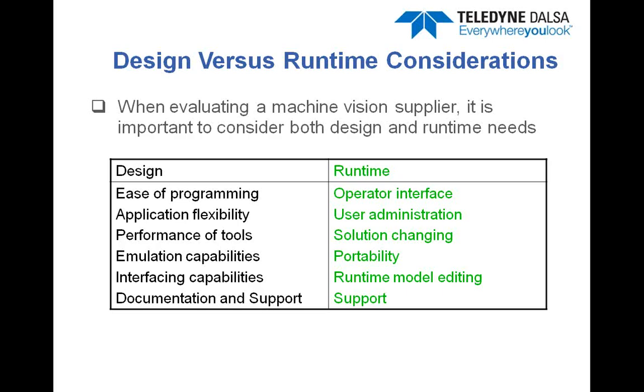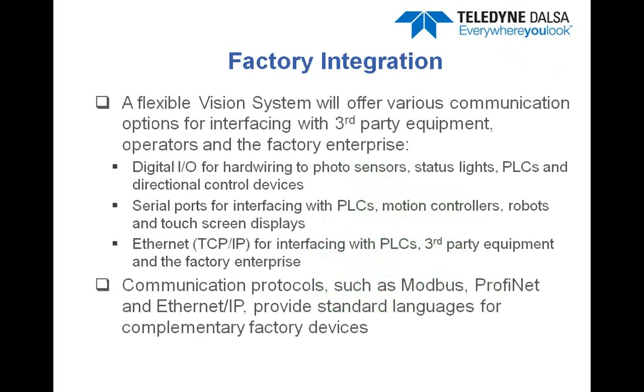A flexible vision system will offer various communication options for interfacing with other equipment. Digital I/O for hardwiring photo sensors, status lights, PLCs, and solenoid kickers are a consideration. Serial ports for interfacing with PLCs, motion controllers, robots, and touch screen displays. Ethernet port, which is one of the more important ones these days, is commonly used to interface with PLCs, other third-party equipment, and factory enterprise systems. Communication protocols such as Modbus, Profinet, and Ethernet IP all provide standard communication languages for interfacing with complementary factory devices.